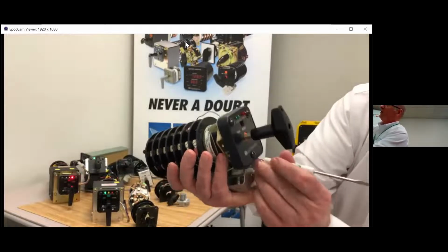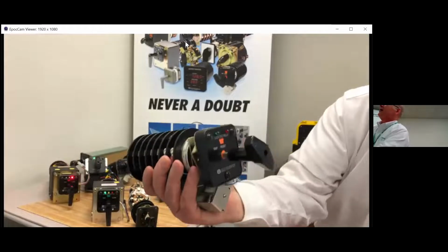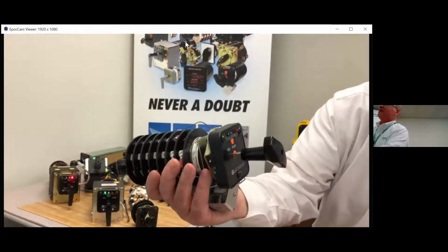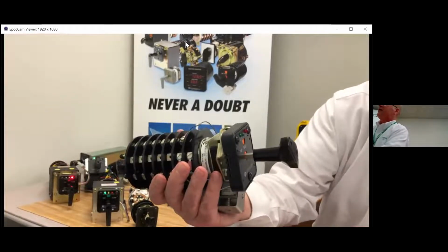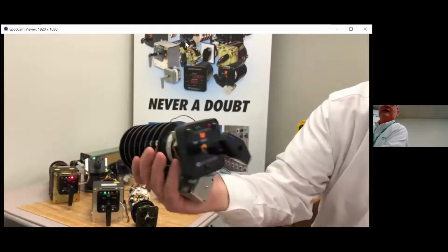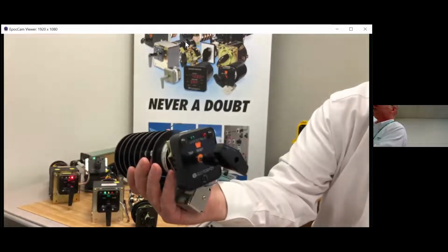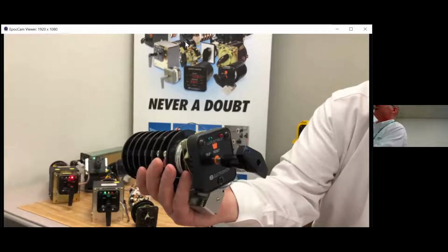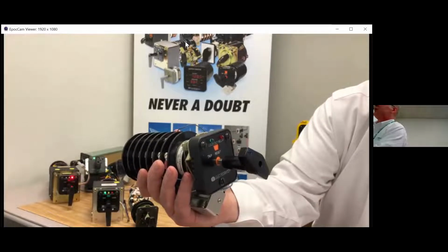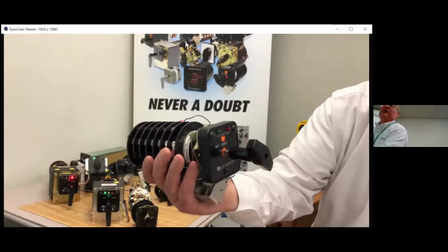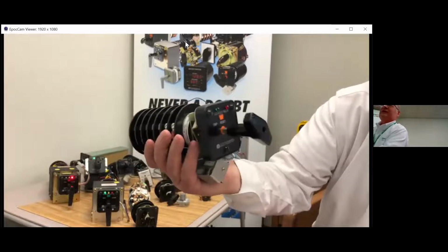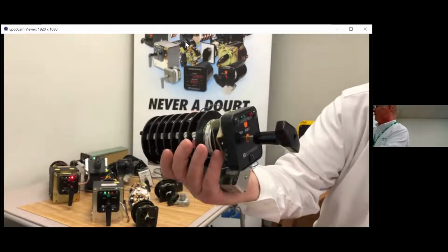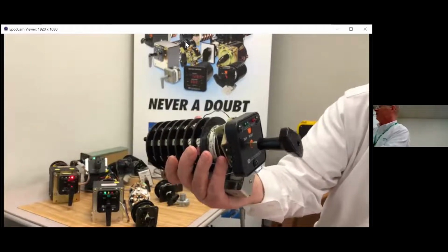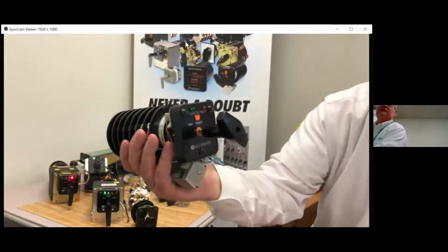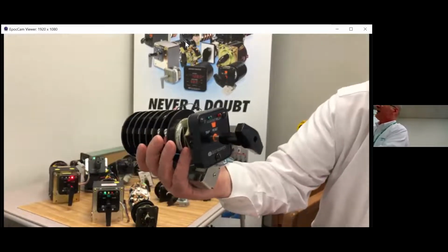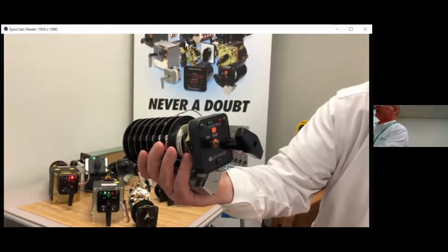So if I go ahead and trip this switch, I have a mechanical flag that comes in and visually gives me a mechanical target, as it's called, and tells me that I'm in the trip position, and my red LED will come on. Now this happens to be not wired to a demo, and I can show you that electronically with one of my electric versions, which I will shortly. So that's how this operation works.